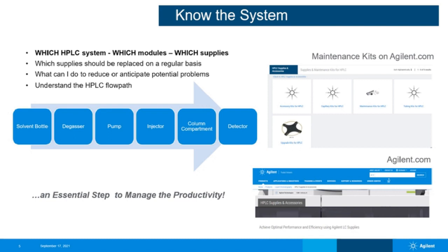Some parts in the HPLC system have to be replaced on a regular basis. Knowing your system, which HPLC system, which modules in the system, which supplies, is key to keep the productivity at the top level. Identifying the maintenance parts and doing a regular maintenance using the kits will help to reduce instrument downtime. Knowing how to find the right supplies on the Agilent.com web page will help to best manage the productivity. And finally, understanding the flow path in your HPLC system will avoid long and costly troubleshooting in case of a blockage or a leak in a capillary or in a connection.